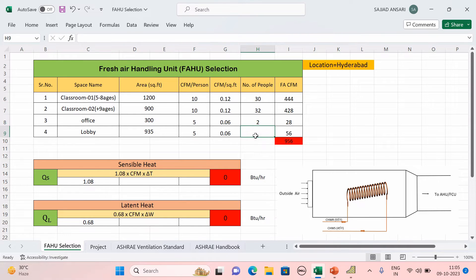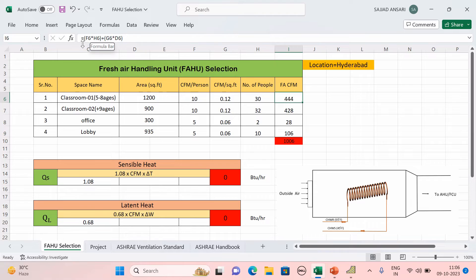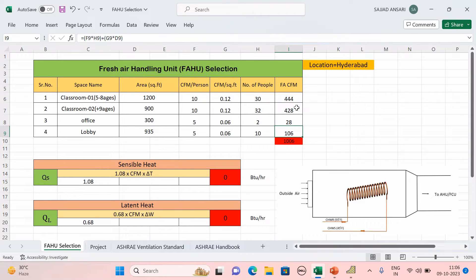For Office you get 2 people, and for Lobby 10 people. The formula applied is: CFM per person × number of people + CFM per square feet × area. Applying this formula gives 444 CFM for Classroom 1. Calculating the same for each room, the total fresh air CFM is 1006 CFM.